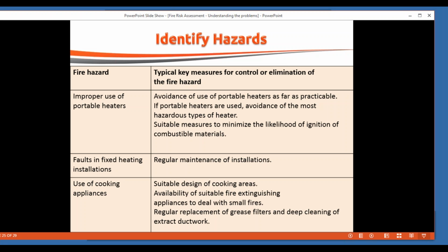So even in relation to relatively small fires, staff have been trained that in the event of a fire, it was important to get out and not to attempt to tackle the fire with firefighting equipment. And that had been identified in the fire risk assessment, and as a strategy for protecting the pupils and the staff in the particular school, that probably was a way to go. It probably wasn't particularly popular with the insurers, because obviously even relatively small fires, if they're going to be left, are potentially going to develop.